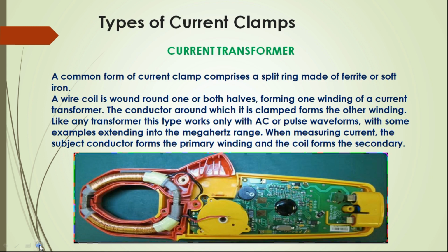Now, types of current clamps. First, current transformer. A common form of current clamp comprises a split ring core which is made up of ferrite or soft iron. A wire coil is wound around one or both halves, forming one winding of a current transformer. The conductor around which it is clamped forms the other winding. Like any transformer, this type works only with AC pulse waves, with some examples extending into the megahertz range, that is MHz range. When measuring current, the subject conductor forms the primary winding and the coils form the secondary.